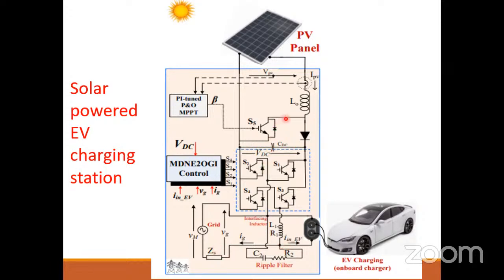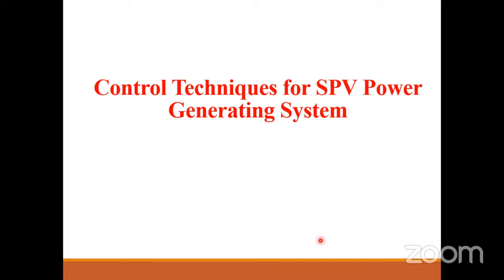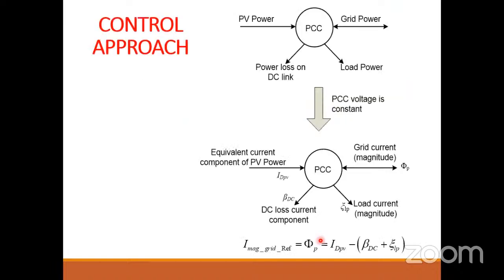At that time we check the behavior of the load. If the load wants heavy harmonic currents, we generate that amount of current from this converter for the local loads, so the burden does not come on the grid even in the daytime. At night, when solar is not there, we generate only harmonic current for these local loads to feed local demands. So this behavior is included in our control, working for both day and night.